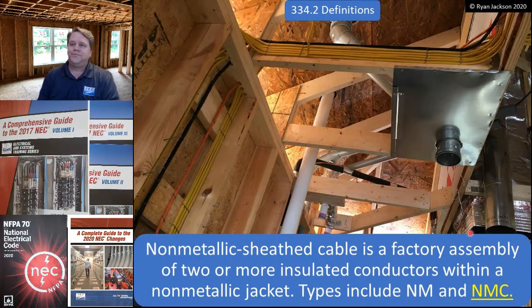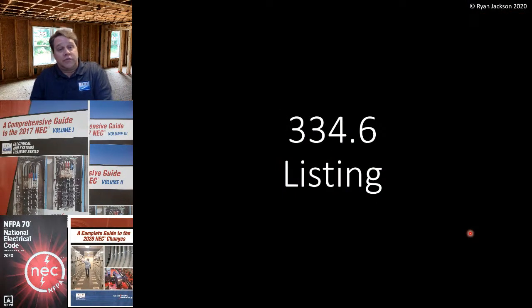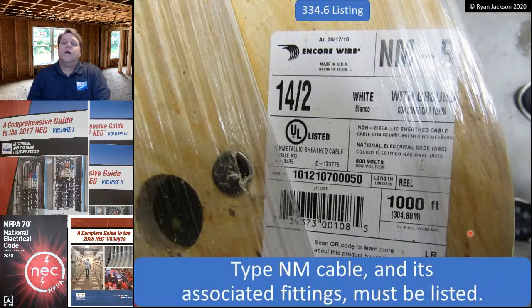It covers NM cable. We got a requirement in 334.6 for listing. NM cable and its associated fittings must all be listed products. Now, the requirement for the cable to be listed has been in the code for a few different code cycles, and this cable, of course, is listed. We can see from our label here that this is a listed product. Easy enough, you buy a listed roll of cable, and it makes sense. I mean, this is the backbone of the electrical system of a lot of buildings in the United States, so we want listed products. New to the 2017 code, its associated fittings must also be listed.